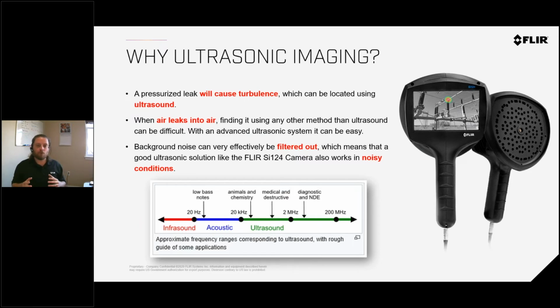Similar to what we talked about with gas imaging, how we tune our lenses to certain gases and certain wavelengths, we can do the same thing with ultrasound. Sound also goes off a wavelength or frequency. You have infrasound, acoustic, and ultrasound, and you can be anywhere on this wavelength or frequency. What we're looking for is a specific area we try to pinpoint for that potential equipment starting to degrade.